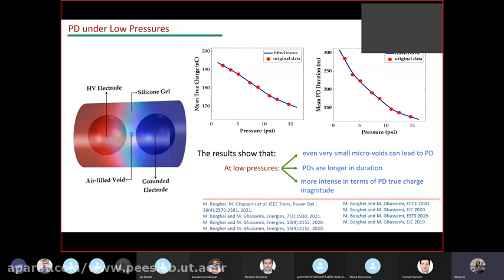This is a study FEA model that we developed. Here I have two electrodes, spheroid shaped, one HV and one grounded, with an air-filled void of micrometer size between them, and silicone gel in between. This represents a case that simulates a power module, and we could see that even very small microvoids can lead to PD.